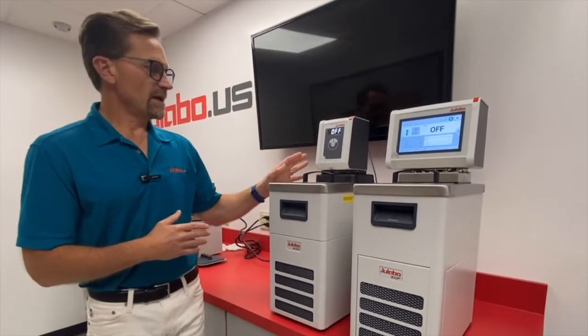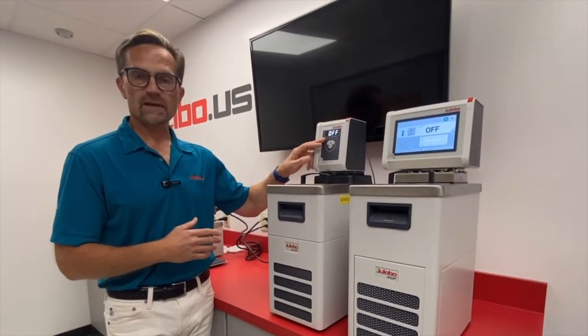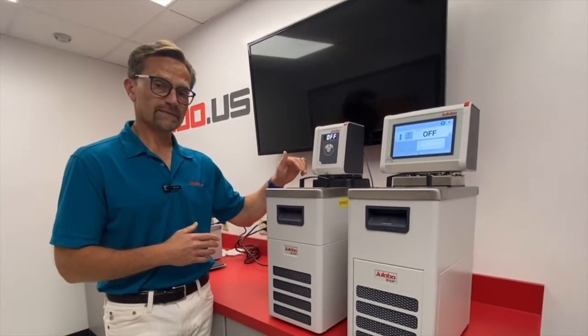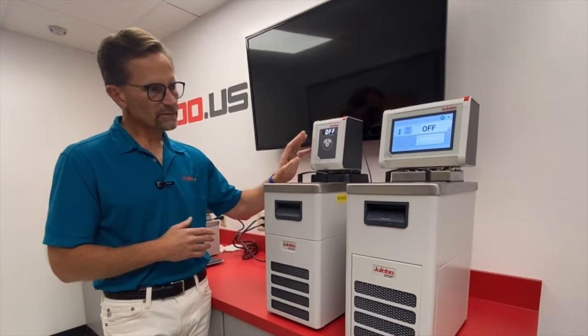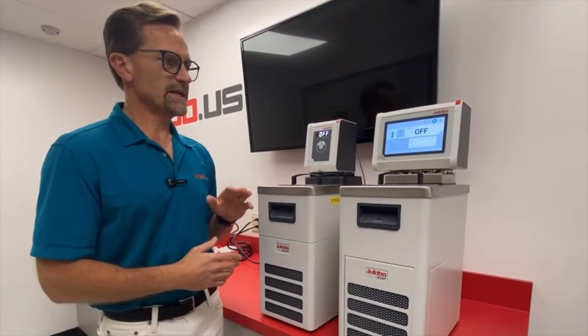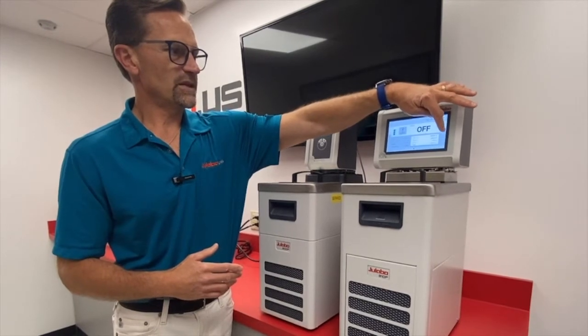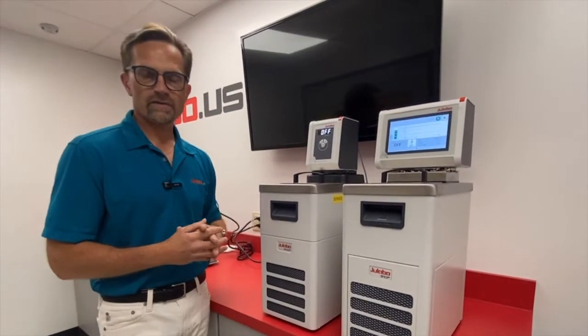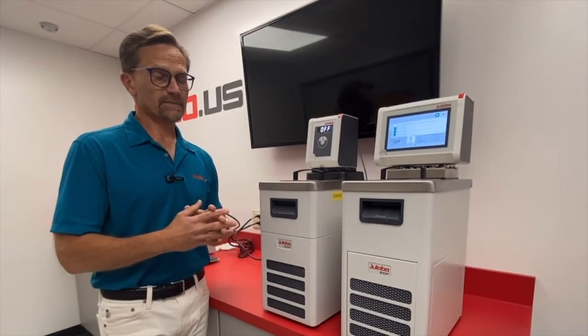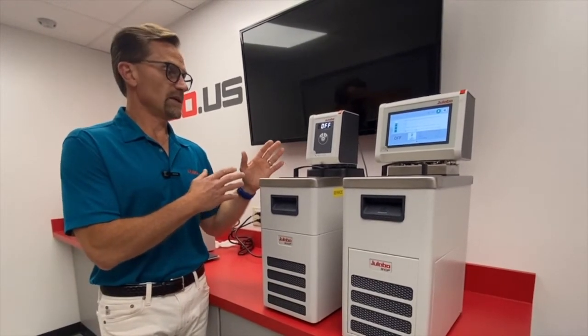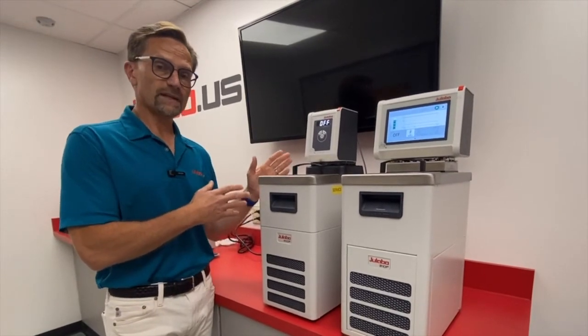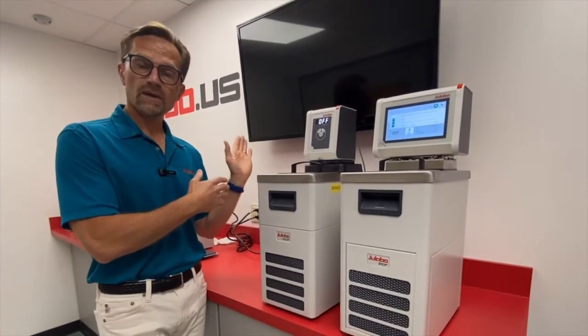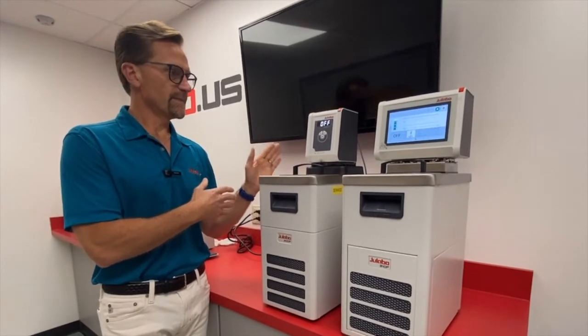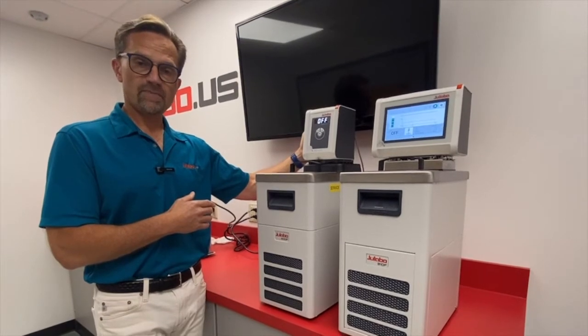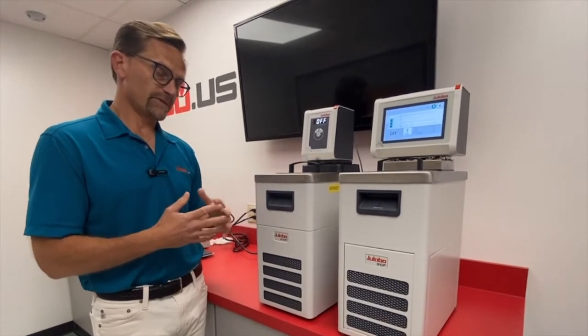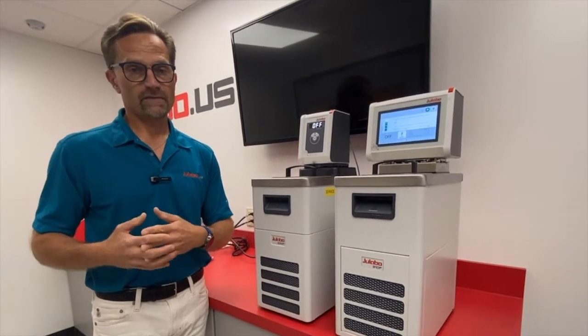On the CORIO, the user interface is simple. Set the temperature, internal temperature regulation only, and there's an integrated timer. With the MAGIO, you have a color touch screen with multiple views for information, graphing, also a wide variety of I/O and programmability. So for the CORIO CD models, the only input-output on the unit is a USB-B port, which you can use to communicate with an external PC or PLC. There is also a USB-A port for data logging and capture, for saving that onto a PC later, for example.